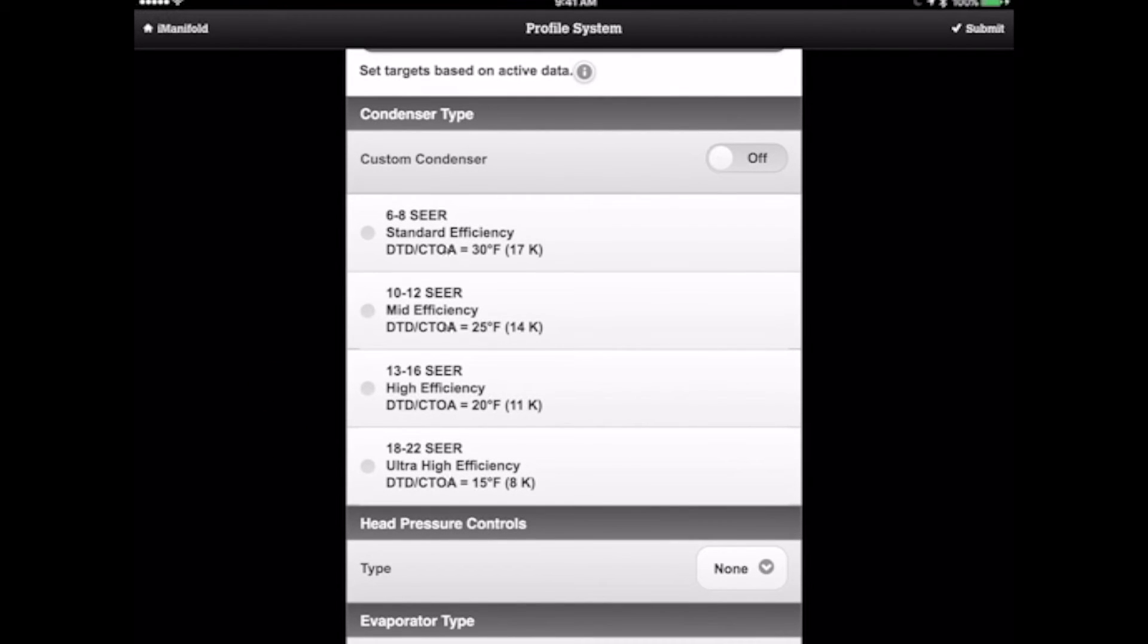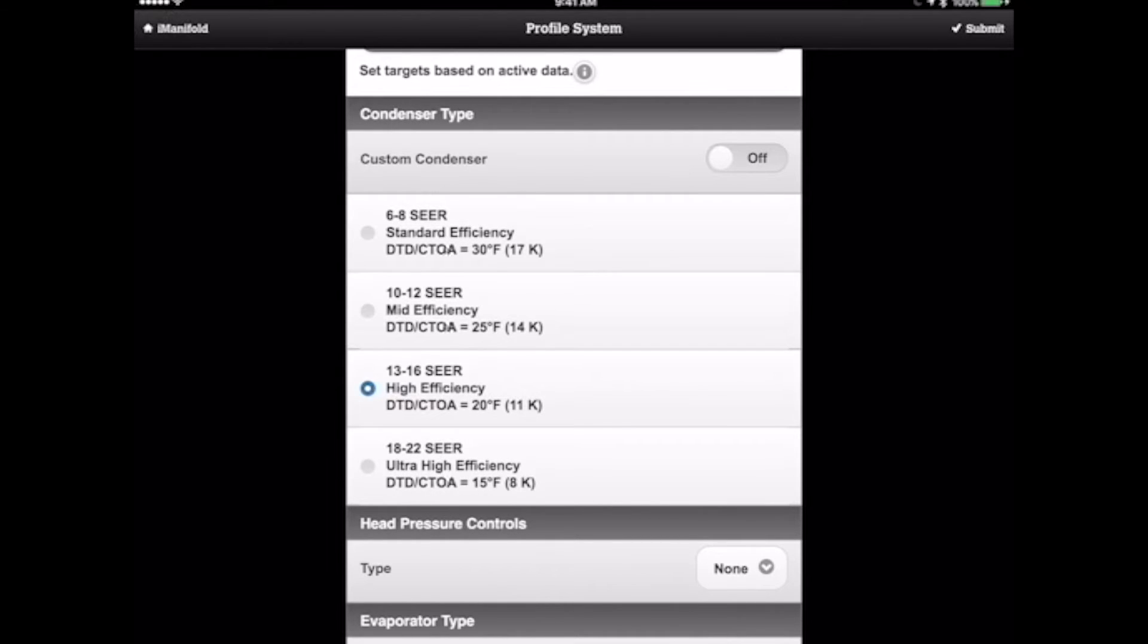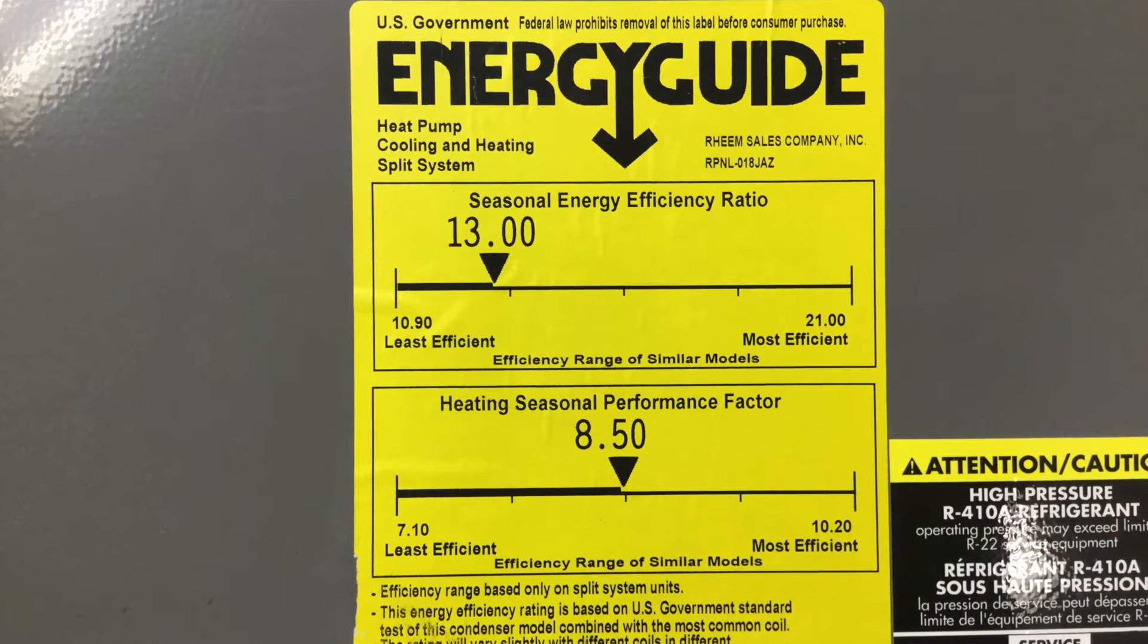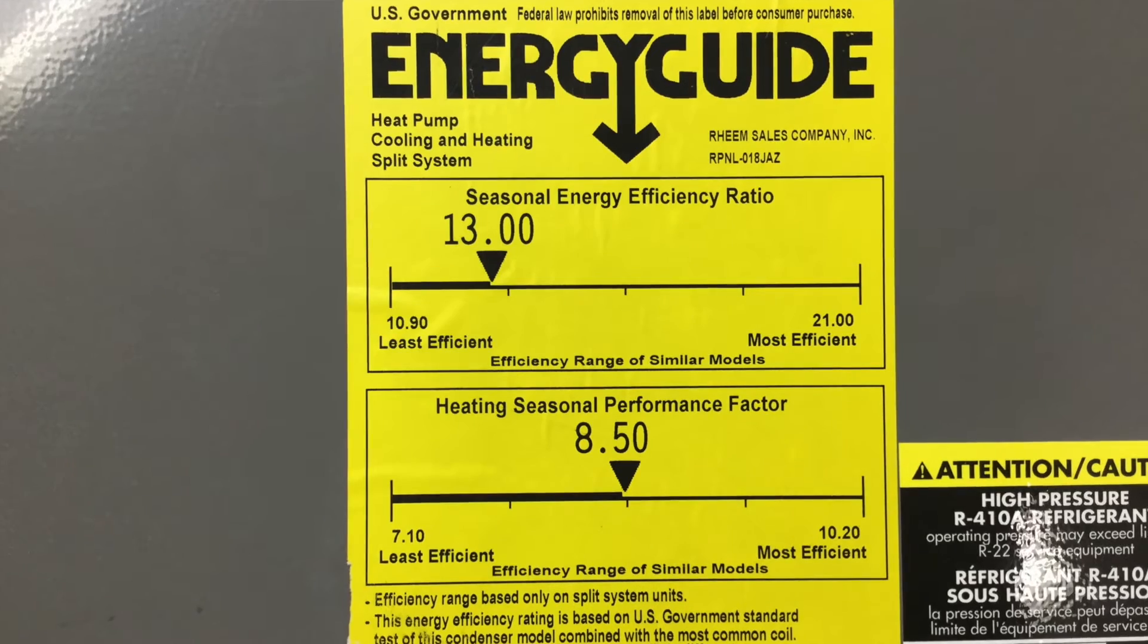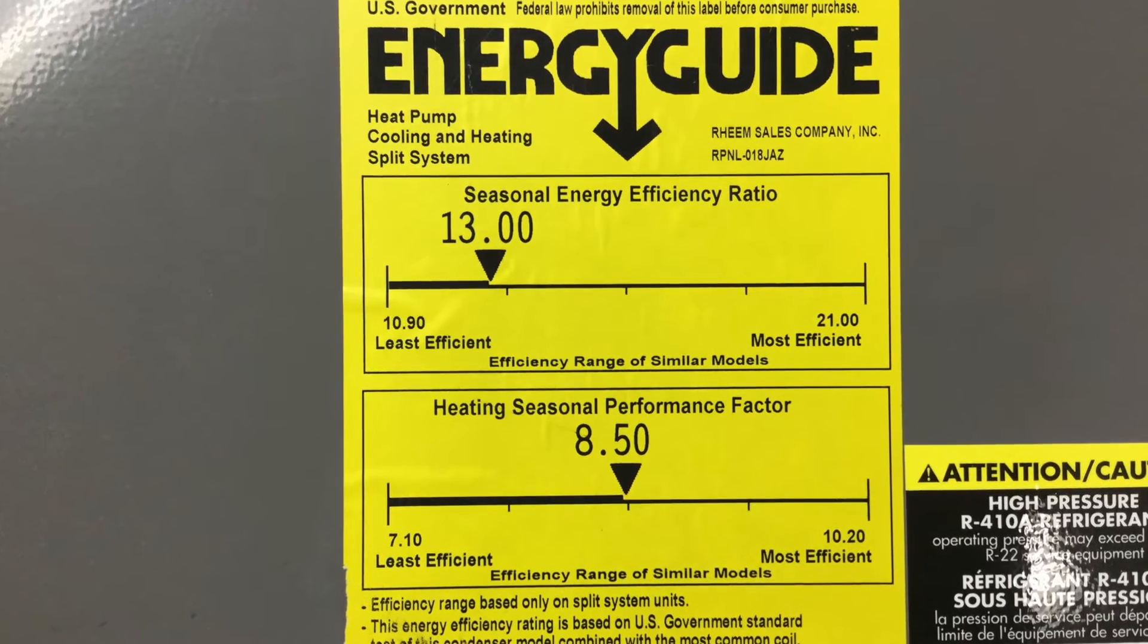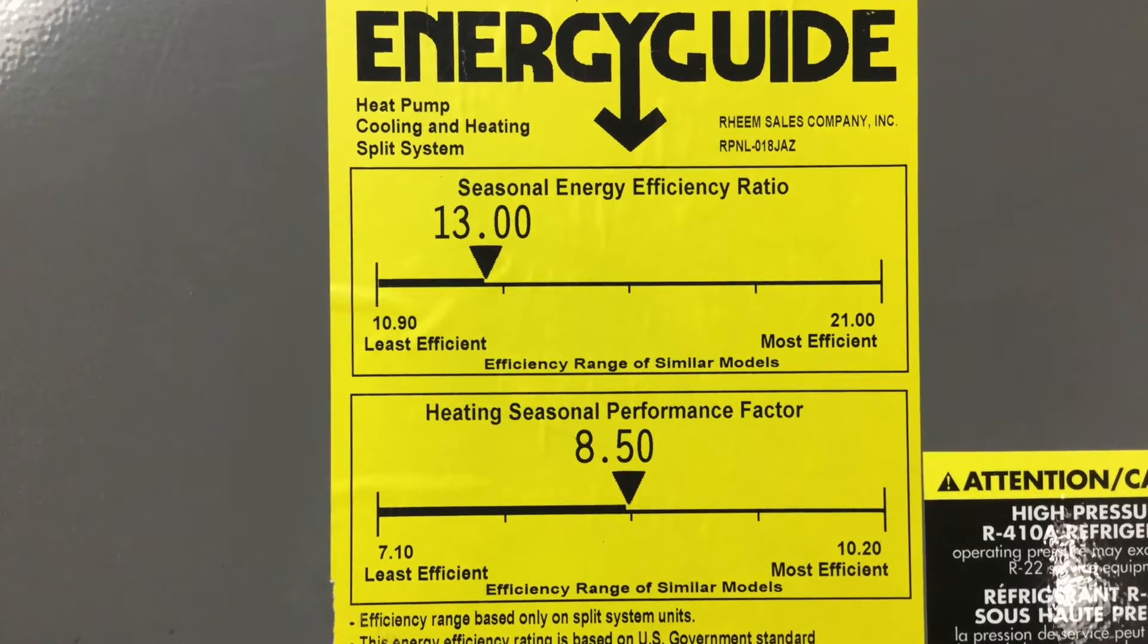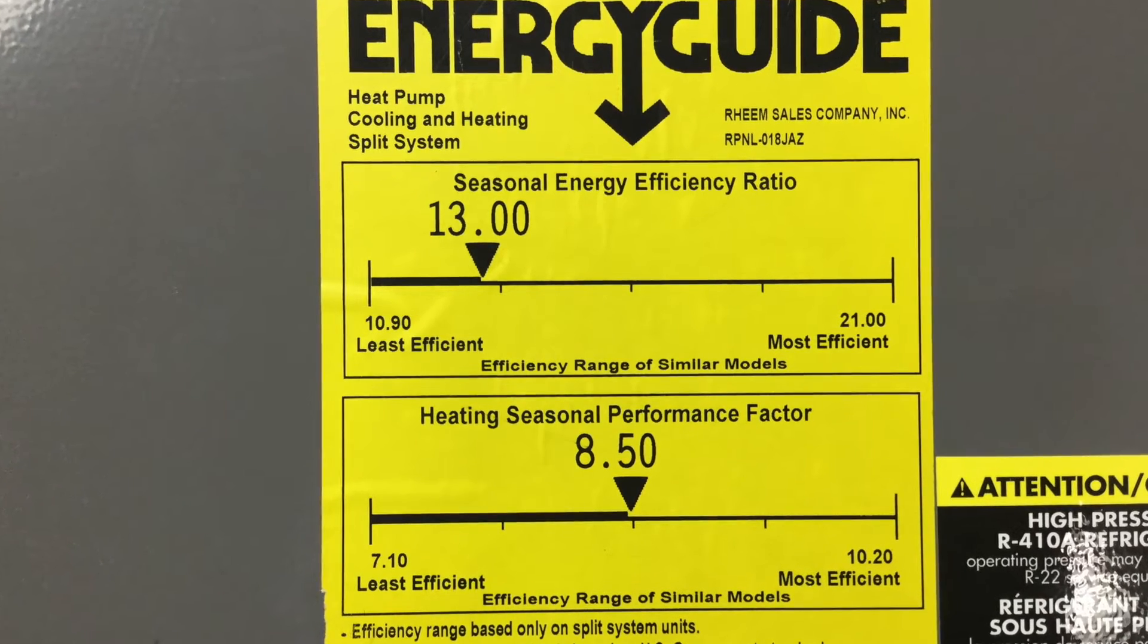So to determine the type of condenser, you have sort of wide ranges here. Most of the stuff we run across today is between the 10 SEER to 22 SEER range. You don't see a lot of 6 to 8 SEER equipment, but it's still out there. In this case here, we'd have a 13 to 16 SEER piece of equipment. That information can come from multiple places - from a model number, or just as simple as looking at the manufacturer's energy guide label. You can see on this energy guide label, it's quite clear this is a 13 SEER system.